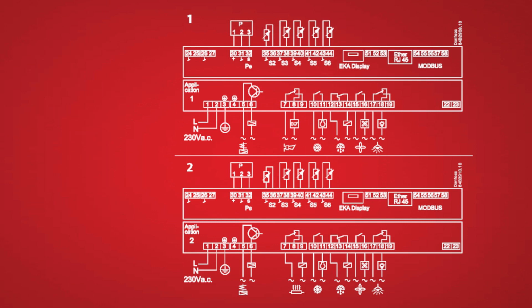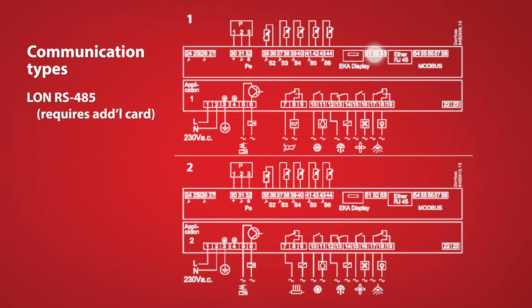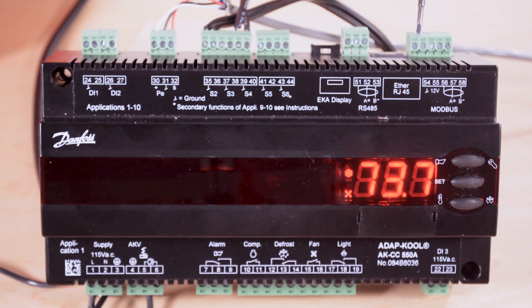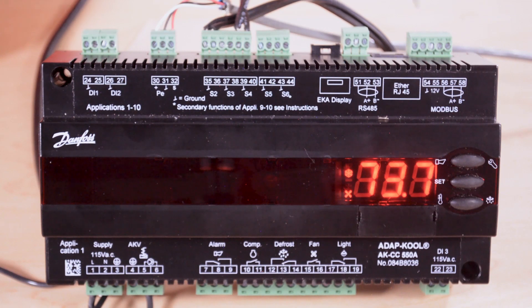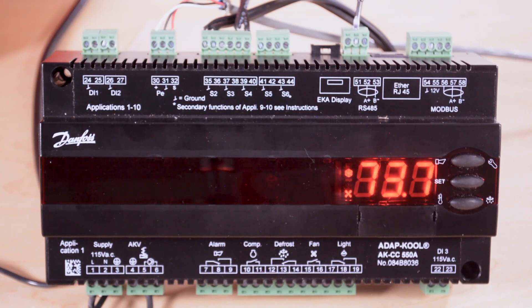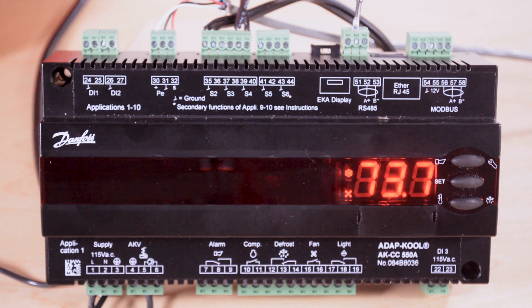Going on down the line we have communication inputs. We have two options on this controller. There's the LON RS-485 and the built-in Modbus RS-485 communication option that'll allow communication back to your system manager. The Modbus option is built in. If you want to use the LON RS-485 then we need to install the communication card.